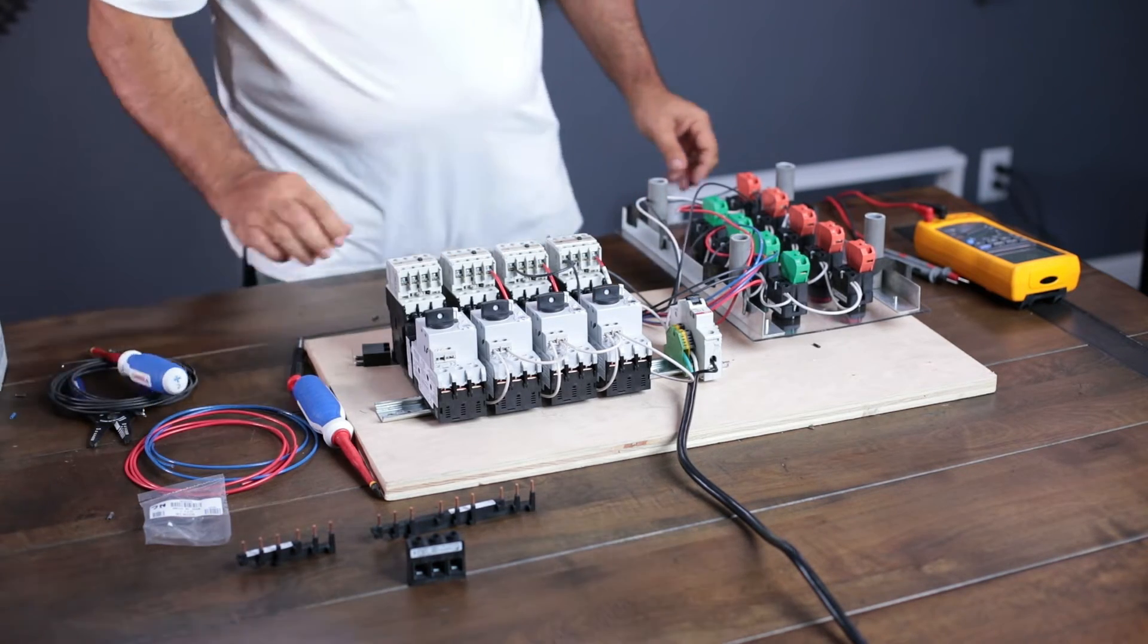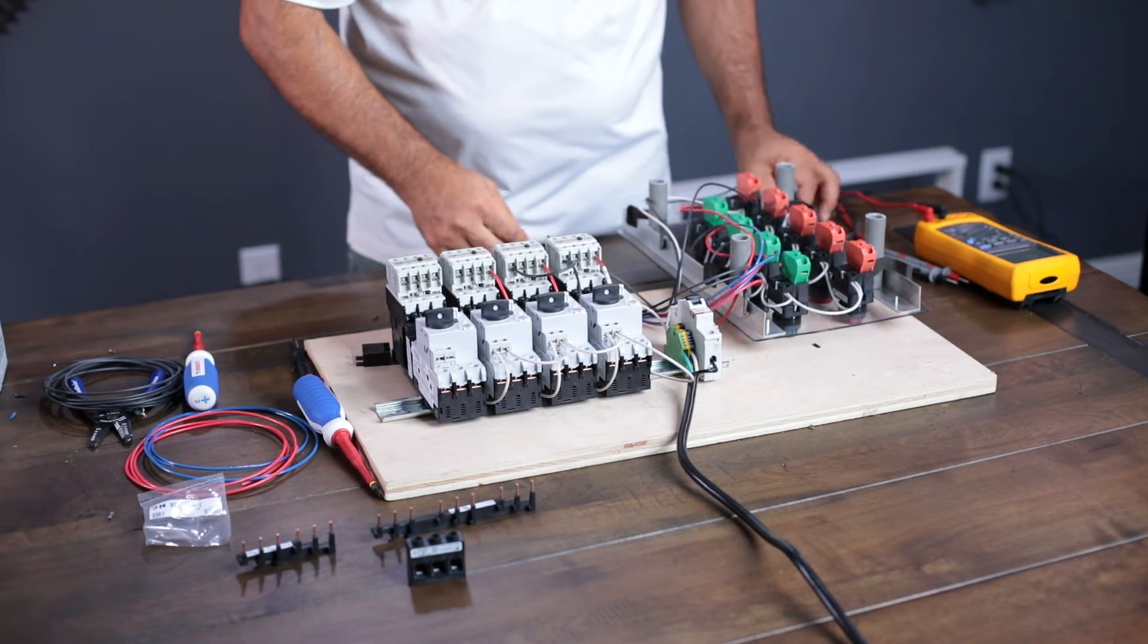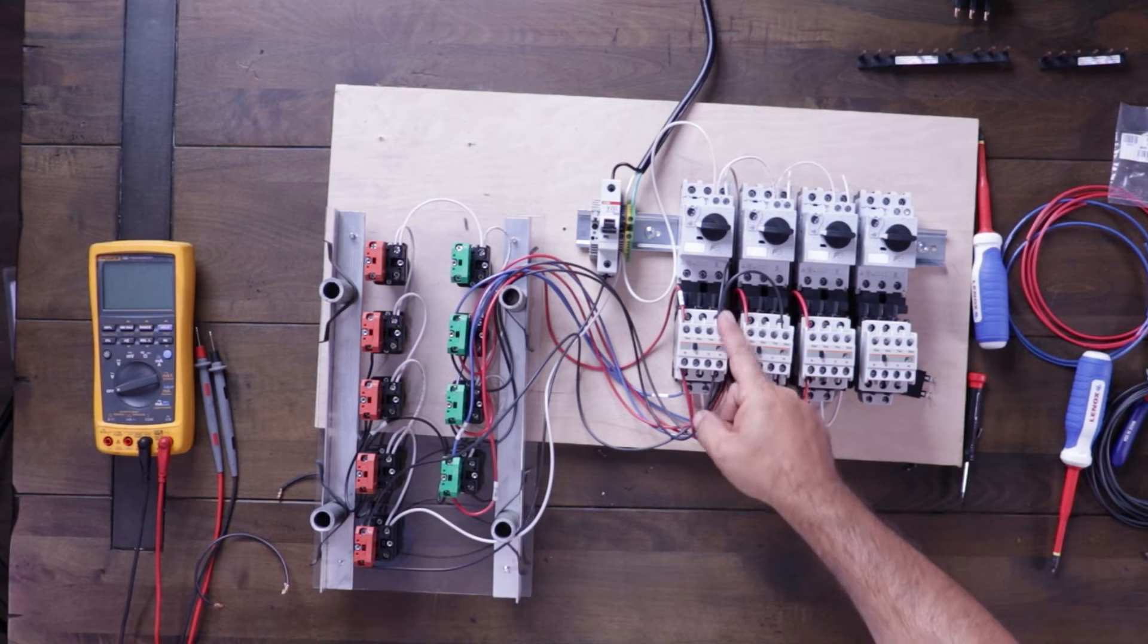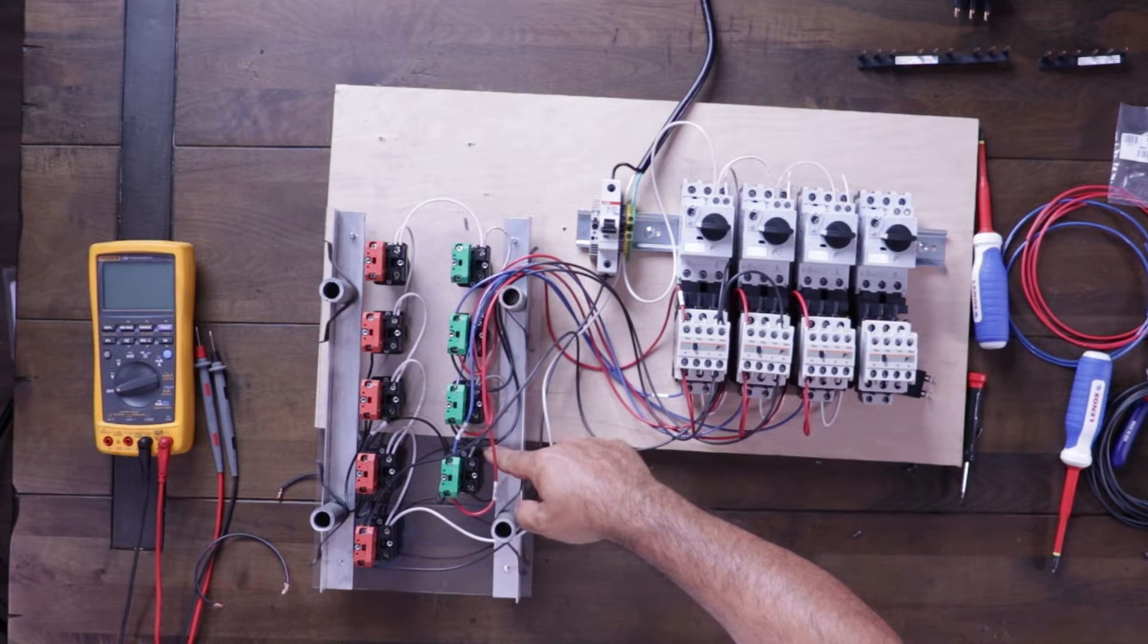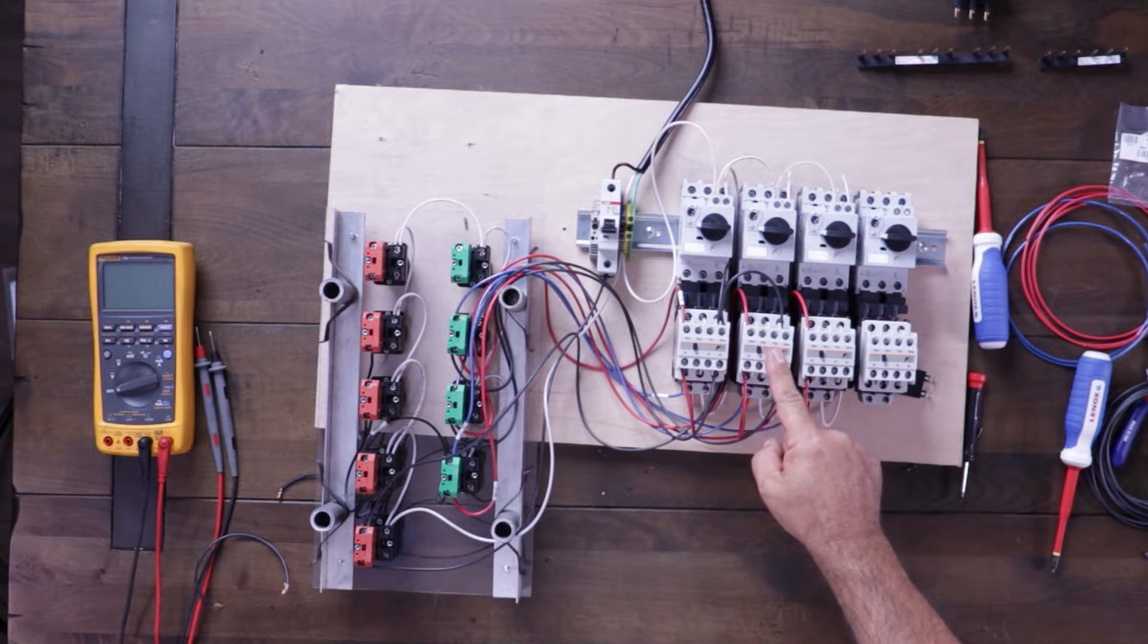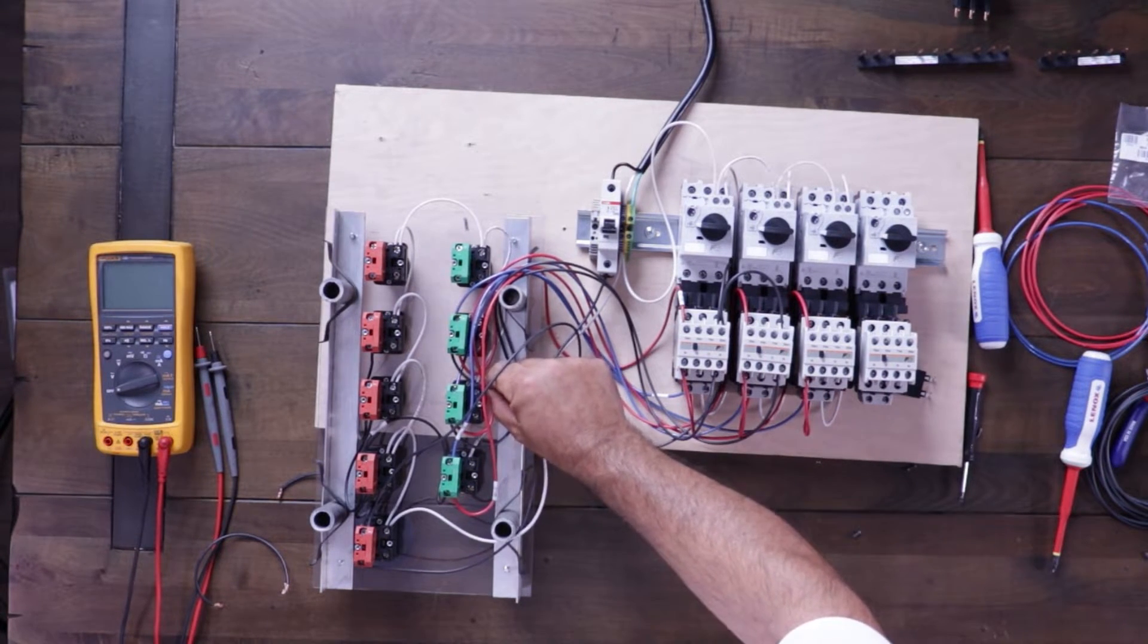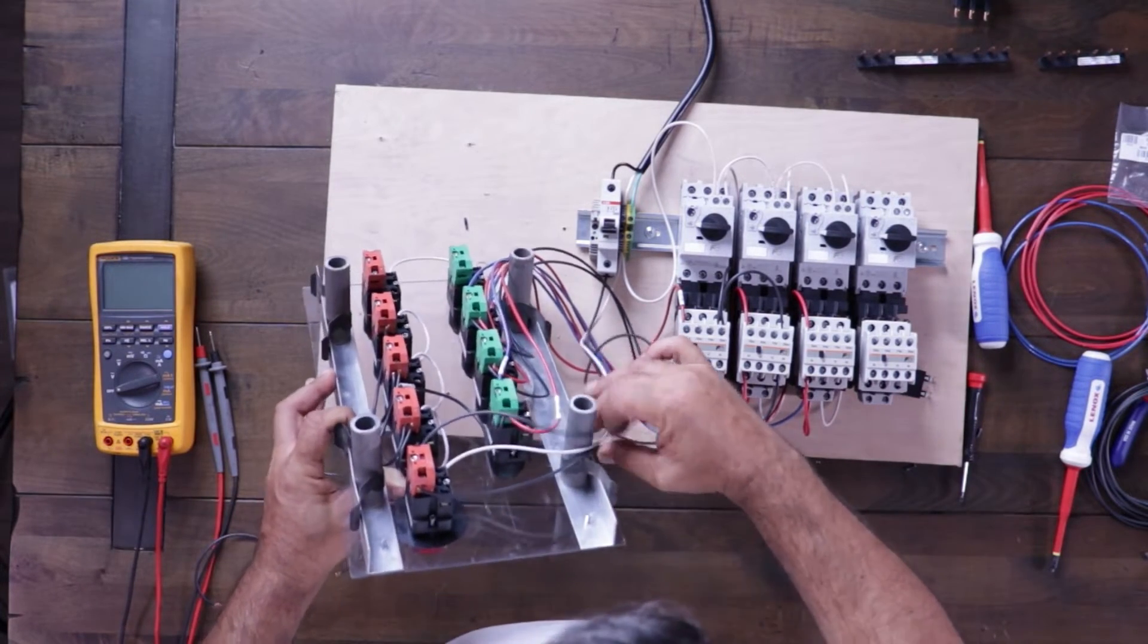Alright, so when the top side always has power, if our e-stop isn't pushed, when motor starter number one comes on, it will feed power to the start button on motor starter number two. When the motor starter number two is on, it will feed power to our start button from motor starter number three, and it will allow those to operate in sequence. Let's flip this over.